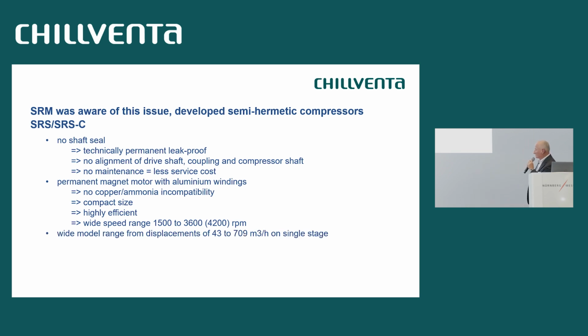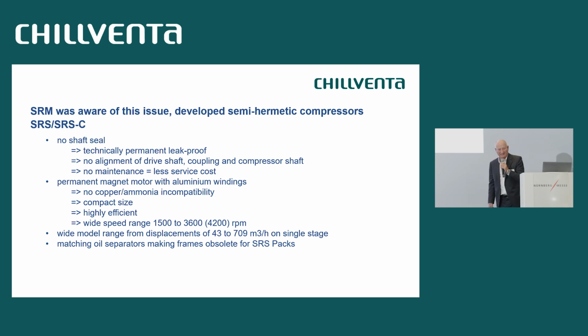The model range we have got is from displacements of 43 to 709 cubic meters per hour on single stage, single compressor applications. Oil separators, which we have got, and they are matching to the compressors, make frames obsolete and reduce cost. Cost in steel, but also cost in mounting, in welding, which all in the end adds up.